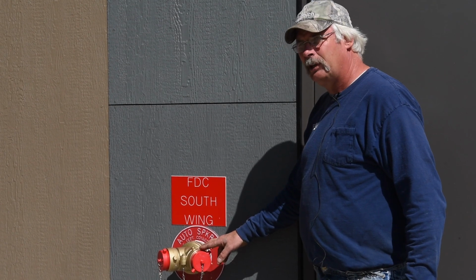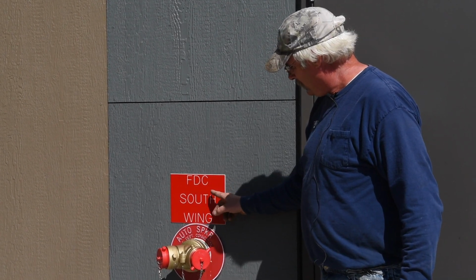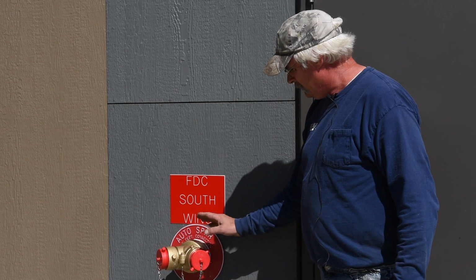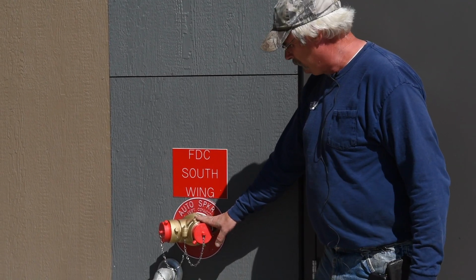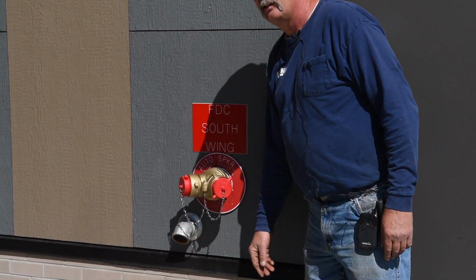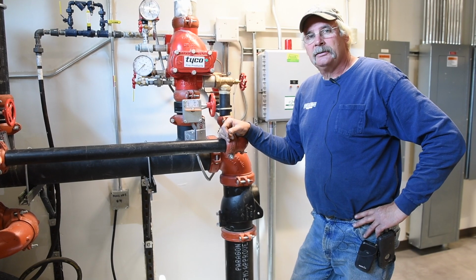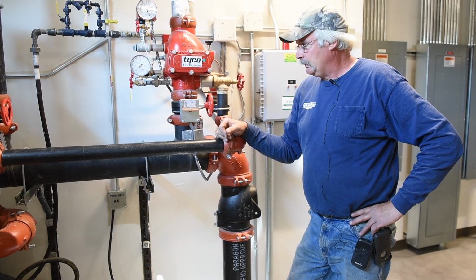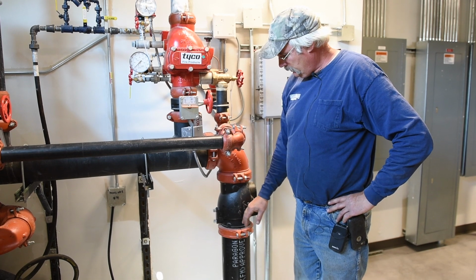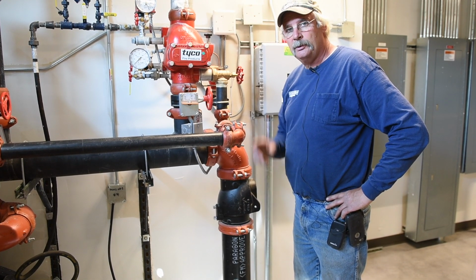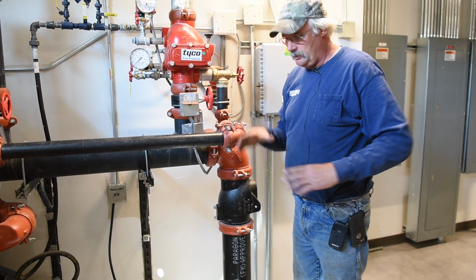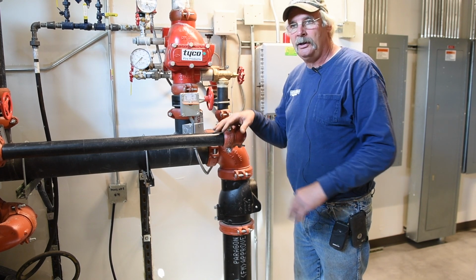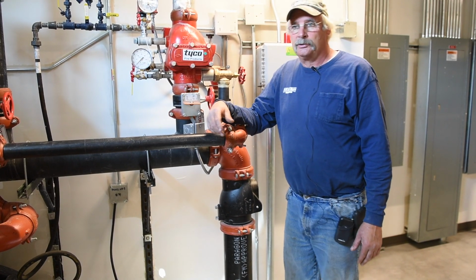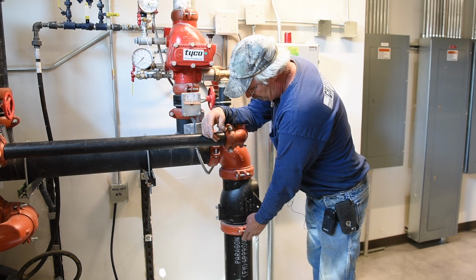Now we're at the south mechanical room, fire department connection, south wing. Again, this is the fire department connection, main drain. Okay, now we're at the south mechanical room, and this is the lead-in coming in from the underground. Straight outside the door you see a red cap flush with the concrete. That is your shut off to shut this underground feed off.